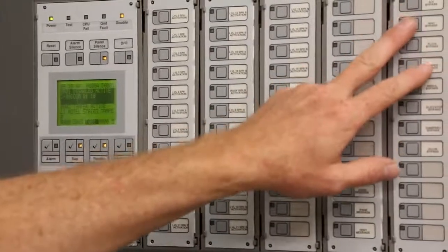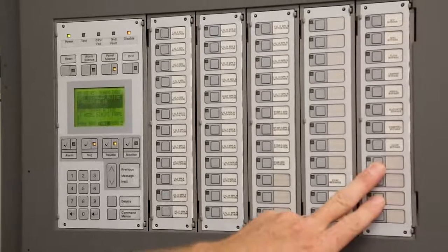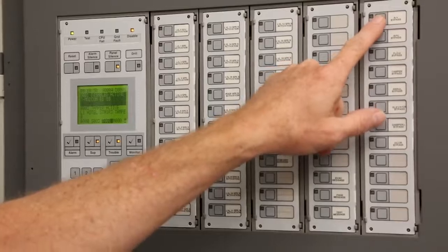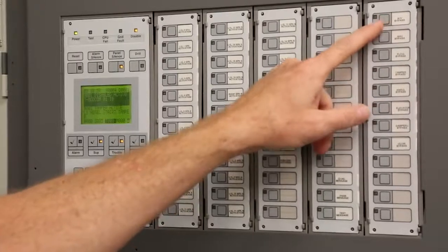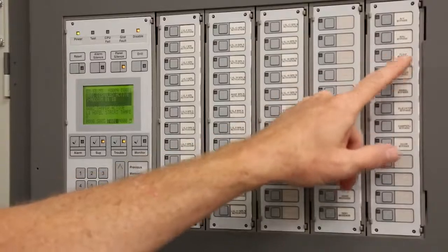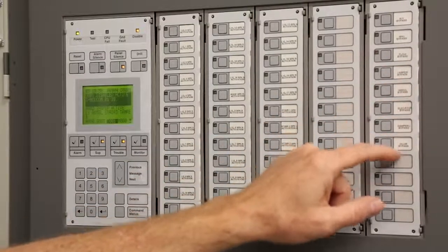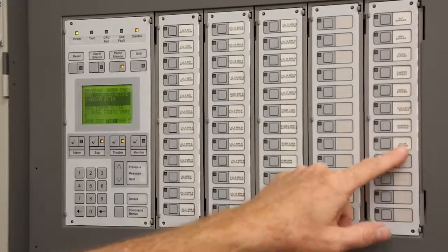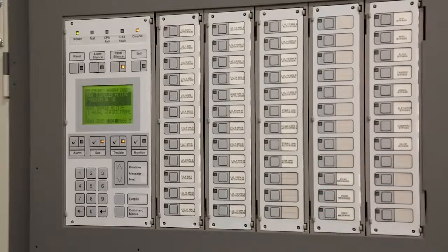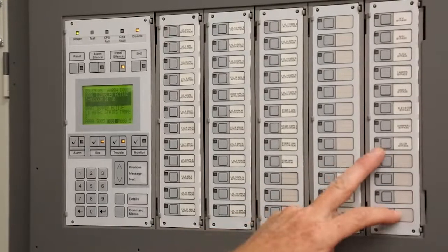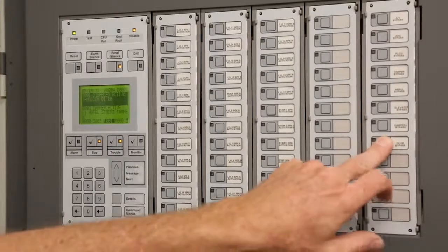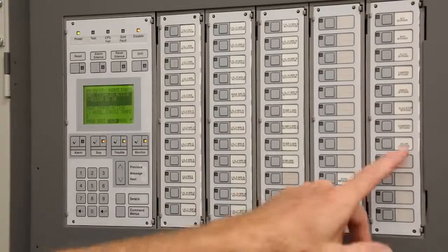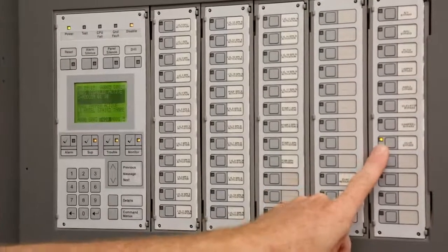Basically, on this side over here, we have bypass switches. So if we're doing any testing, you can simply hit AV bypass. It will light up and flash. And you have air handler bypasses, flow, tamper, ANSUL, elevator, dampers, and door bypass. So for instance, if we're testing and we wanted to bypass the doors, you simply just push the button one time. Right now, it'll flash when it's activated right there.